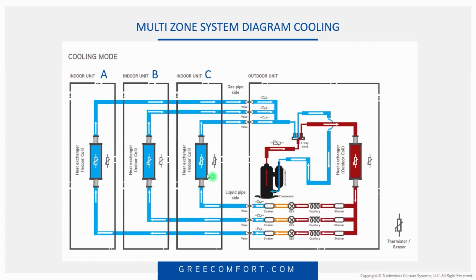Because if that indoor unit is calling, it's got to be able to monitor that refrigerant flow going through that indoor coil, because that's only one. If I've got this one calling and that one calling, I've got to be able to share my refrigerant flow to both of these coils, and then thirdly, this one. So let me put this in real world troubleshooting for you.